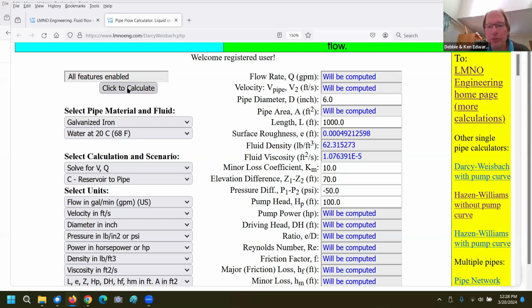So just for fun, I've keyed in a diameter of 6 inches. So this would be an internal diameter for a length of 1,000 feet. Minor losses of 10. So this is a whole bunch of valves. Each valve is maybe 0.5. So maybe there's 20 valves in here or other stuff. Or, not a valve, but maybe each elbow is around 0.5. Valves can be kind of all over the place depending how open they are.